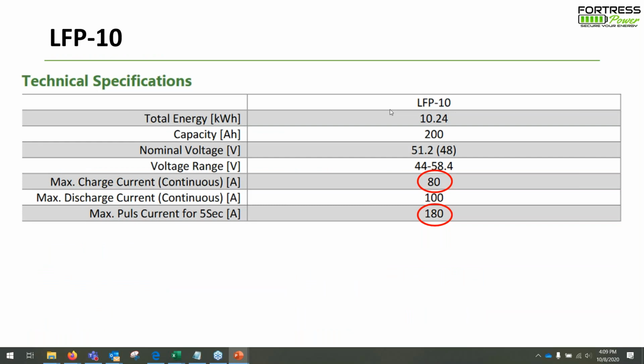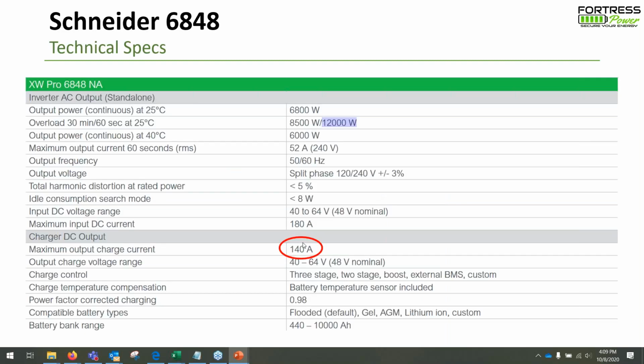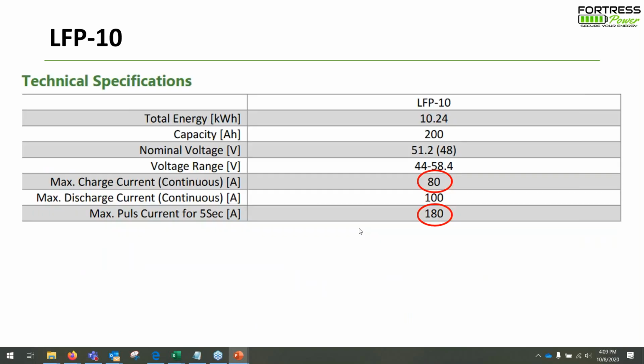If we look at the LFP10 specifications, the max charge current is 80 amps. The max pulse current for 5 seconds is 180 amps, but generally we go by the max discharge current continuous, which is 100 amps. So when we compare this 100 amp max discharge current to the max current of the Schneider of 140 amps, we can see that there's already going to be a problem, and I'll explain why.